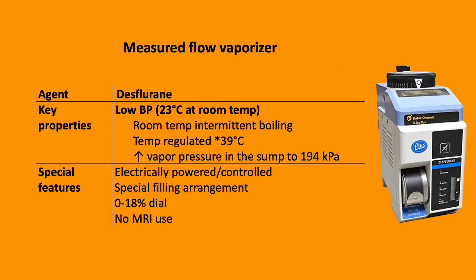Desflurane is different from other volatile agents, and therefore requires a different vaporizer. Firstly, it has a low boiling point, so it would intermittently boil at room temperature. The vaporizer increases the temperature to 39 degrees Celsius, resulting in an increased pressure of 194 kilopascals. Special features of this vaporizer include: it requires electrical power, is controlled by electrical measures unlike other plenum vaporizers, has special filling arrangements, a higher concentration dial up to 18%, and cannot be used in MRI.